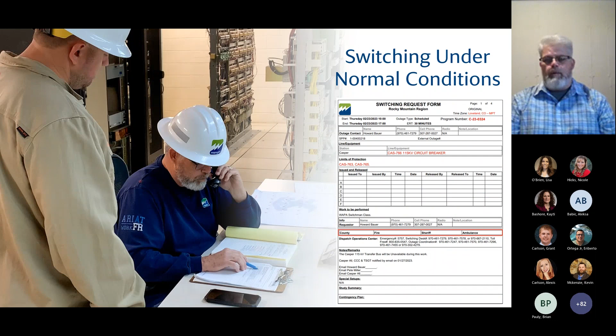When I'm a switchman and I communicate with the system operator, the first thing I do is tell them the program number. For example, C meaning clearance, 23 because it's 2023, and then the program number. It could be anywhere from 1 to 2015. They're listed in sequential order as they start through the year. So in this case, for example, C23, it could be program 144.